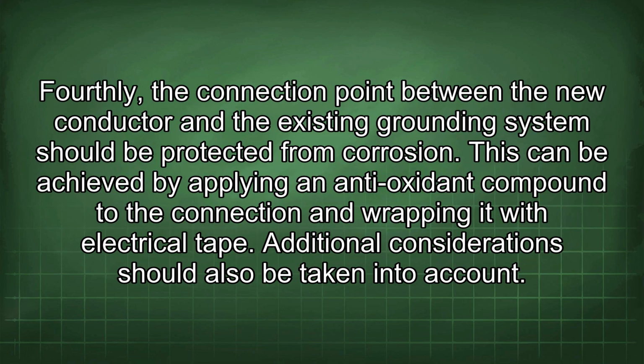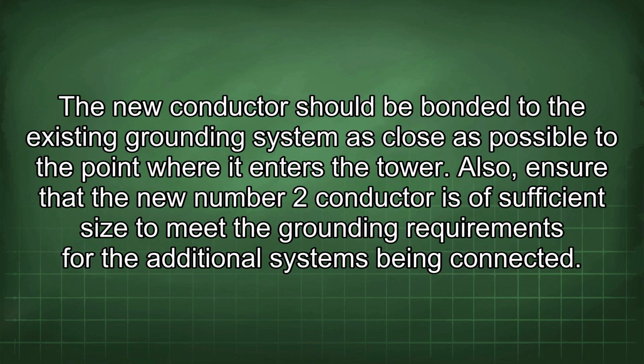Fourthly, the connection point between the new conductor and the existing grounding system should be protected from corrosion. This can be achieved by applying an antioxidant compound to the connection and wrapping it with electrical tape. Additional considerations should also be taken into account. The new conductor should be bonded to the existing grounding system as close as possible to the point where it enters the tower. Also, ensure that the new number 2 conductor is of sufficient size to meet the grounding requirements for the additional systems being connected.